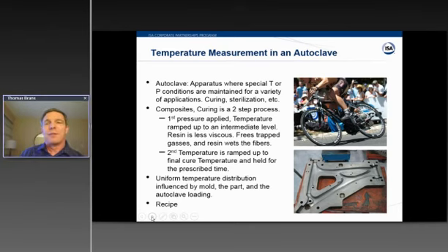Okay, thank you, Katie. Before I get into this next application, a last comment on the previous application with heat exchangers. I didn't mention that when you're trying to measure differential temperature, say across a heat exchanger from the inlet to the outlet, heat exchangers are relatively small compared to a lot of other assets that we're measuring, but it's possible to use two sensors into one transmitter to get the differential temperature. So these features with temperature transmitters allow you to use one temperature transmitter with 2 sensors instead of having to use 2 temperature transmitters. Okay, so with that said on heat exchangers, let's move on to this application with an autoclave.